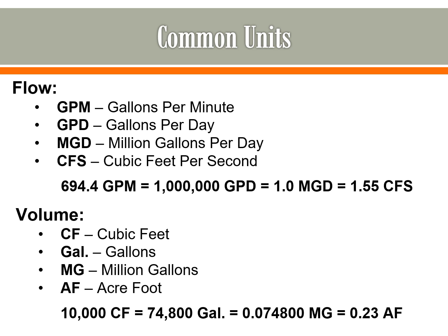And then same with this one. You've got 10,000 cubic feet, which is the equivalent of 74,800 gallons, which is the equivalent of 0.0748 million gallons, or 0.23 acre feet.